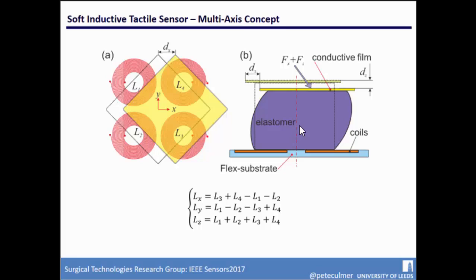If you take your normal measurement where that conducting element is sat equally above all four coils, you should have the same nominal inductance measured at each of those coils. As you apply shear, moving from left to right, the conductor covers more of L3 and L4, so there's a corresponding shift in the inductance seen at those coils relative to coils 1 and 2.